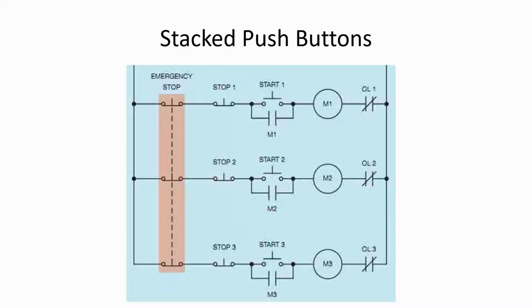One of the advantages of using the industrial push button is that it is stackable. We can stack a number of push buttons one after the other, so that in one actuation, one press, all the push buttons will be activated simultaneously. The number of contacts in each block will be changed in one press.